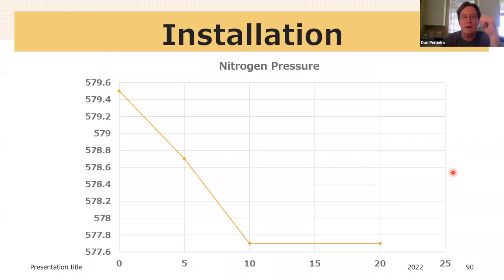This is the beginning of a nitrogen test. You can see it was pressurized to 579.5. And at 10 minutes, it's dropped to 577.7. And then it starts to level out. There's an equalization period where the temperature of the nitrogen sort of equalizes in the system. So you pressurize it and your initial numbers will shift, but then you should get a long period of no change.